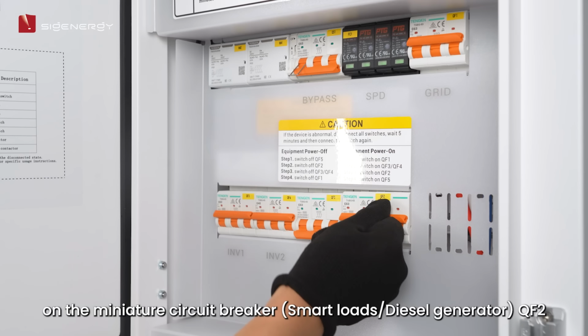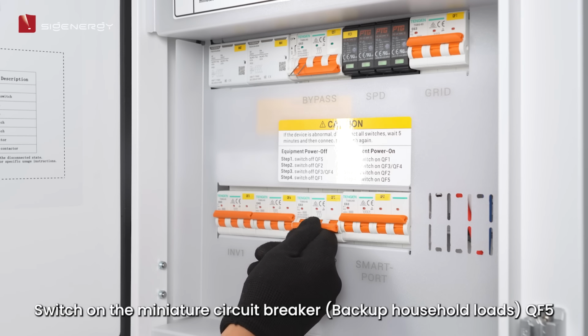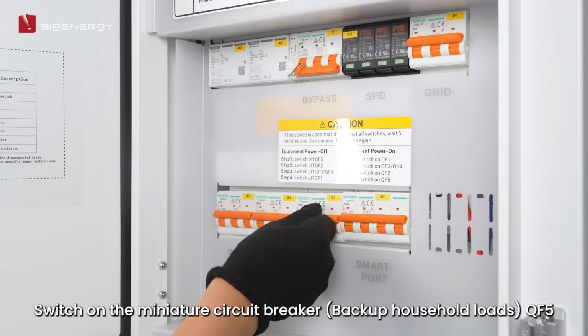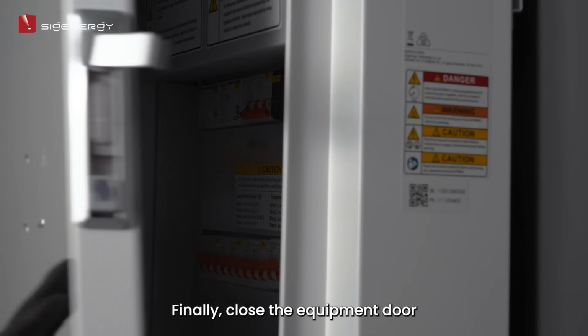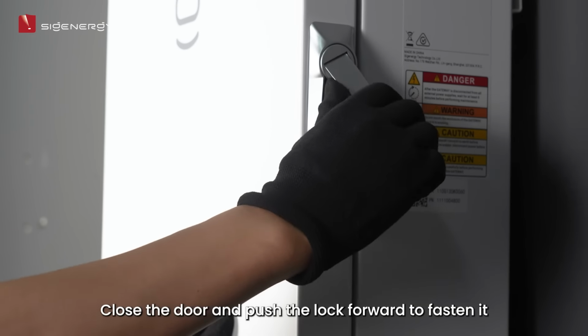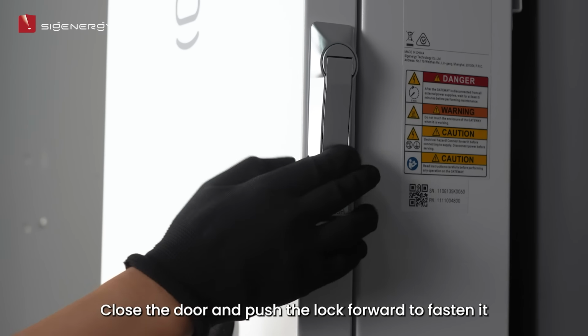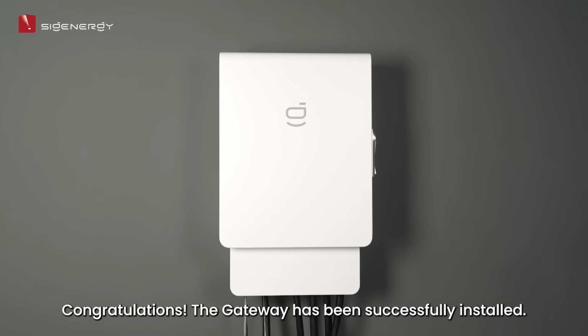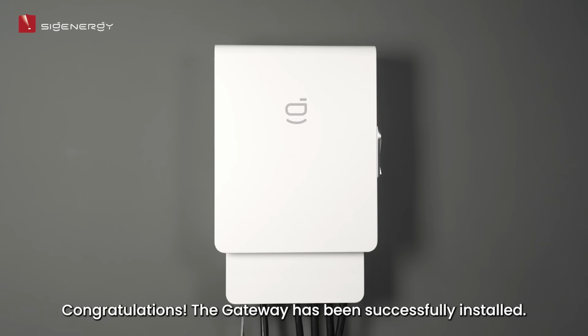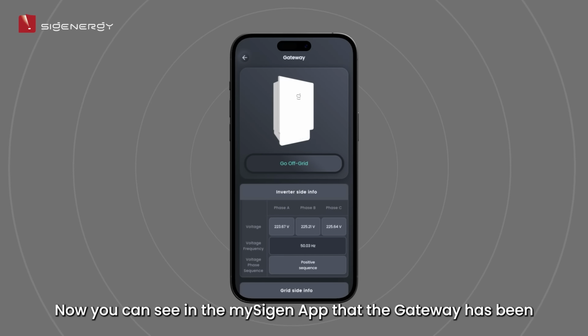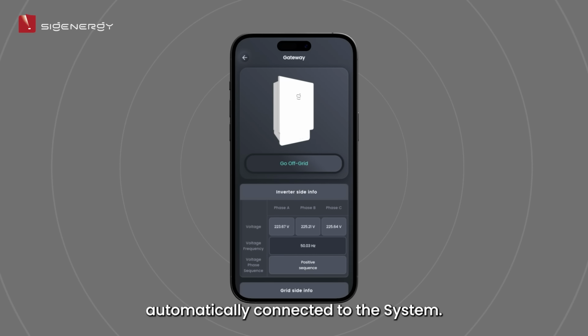Optional switch on the miniature circuit breaker, smart loads, diesel generator, QF2. Switch on the miniature circuit breaker, backup household loads, QF5. Finally, close the equipment door. Close the door and push the lock forward to fasten it. Congratulations, the gateway has been successfully installed. Now you can see in the My Sigen app that the gateway has been automatically connected to the system.